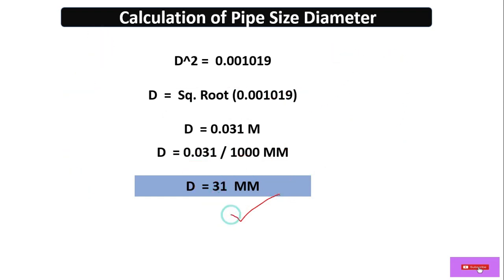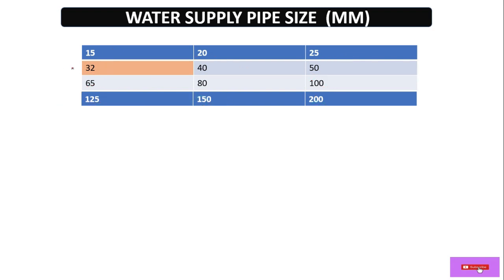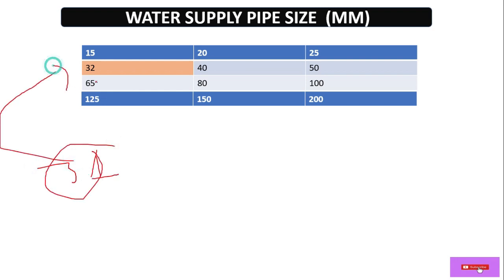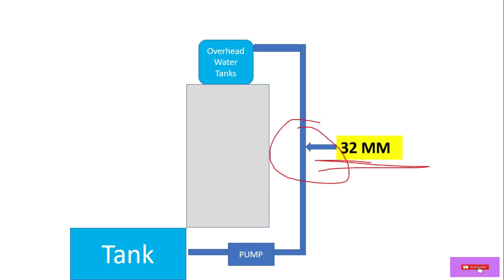The calculated size may not be available in the market, so we select from available standard sizes. Looking at the table of available pipe sizes — 15, 20, 25, 32, 40, 50, 65, 80, 100, 125, 150, 200 mm — our calculated value is 31 mm, which is nearest to 32 mm. Always go for a size higher than the calculated value, so our final pipe size is 32 mm.